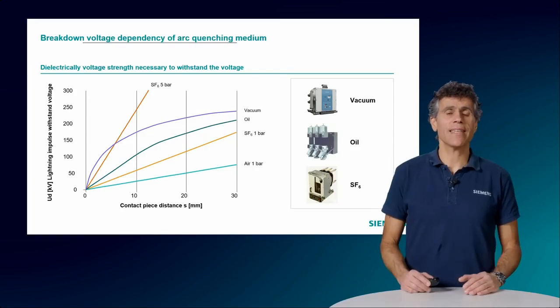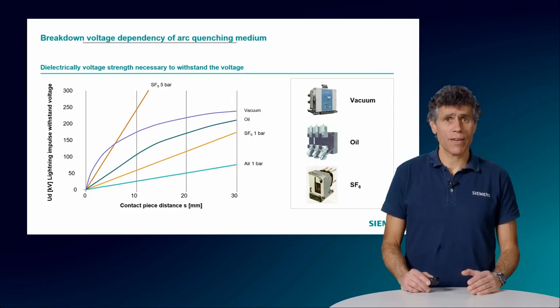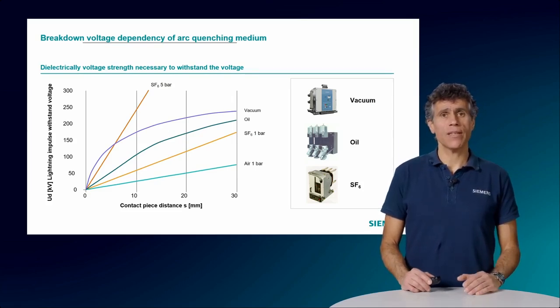SF6 is an excellent insulator. It has a very high dielectric strength. On the other hand, it's a potent greenhouse gas, and it requires careful handling due to its potential environmental impact. Oil is also quite a good insulator, and it's readily available. Its disadvantages are the difficult handling, the potential for leaks and contamination, and the risk of fire.